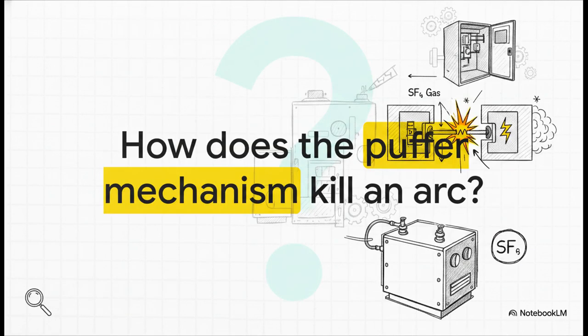But identifying the equipment from the outside is really just the beginning. Sure, you can read the nameplate, spot that legacy breaker, and know it relies on SF6 gas. But do you know exactly how its internal puffer mechanism violently snuffs out a superheated electrical arc in just milliseconds? Think of it like a high-powered bicycle pump: it compresses the gas and blasts it directly onto a separating contact to completely kill an arc instantly.